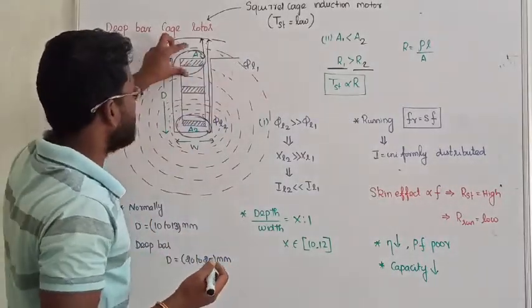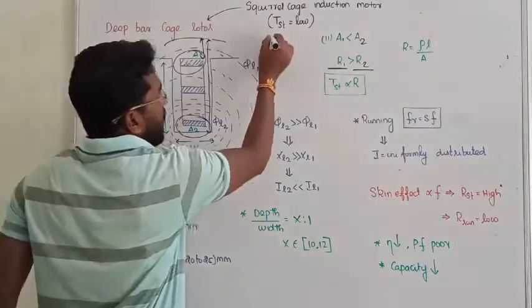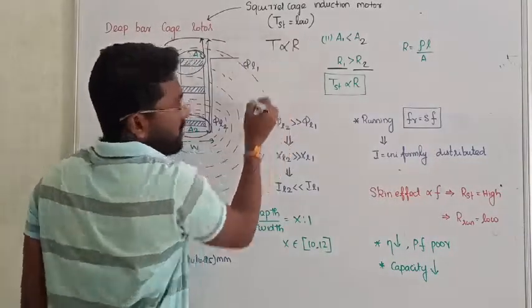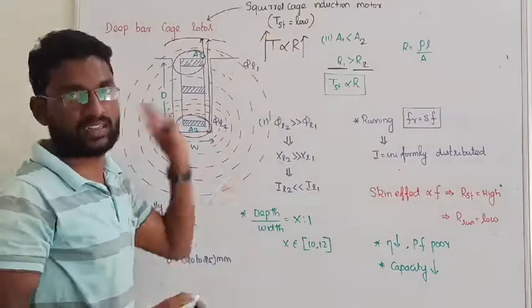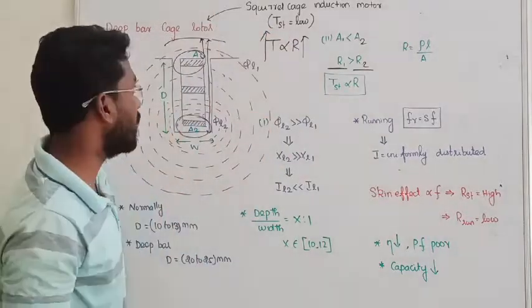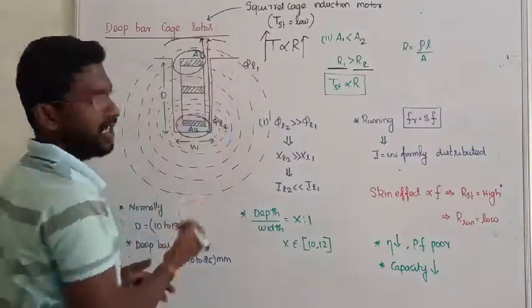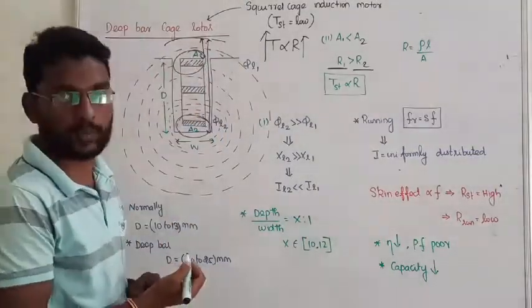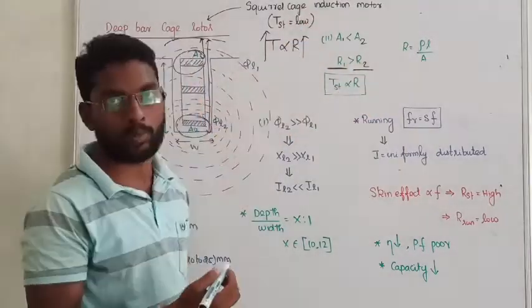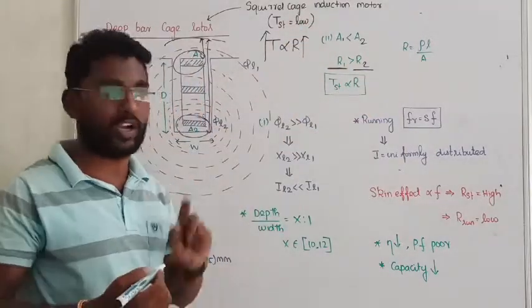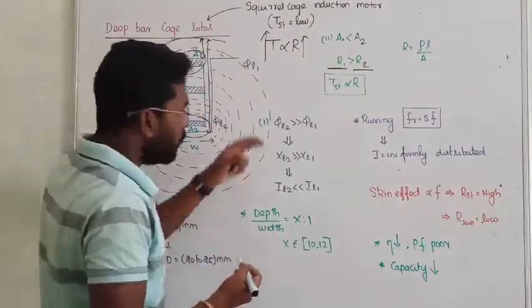Rotor resistance is increased. Starting torque is directly proportional to the resistance, so since the resistance is increasing, starting torque is increasing. That is how we are improving the starting torque with the help of deep bar cage rotor. So depth is increased, resistance at the outer area will change, so that starting torque will be effectively improved.